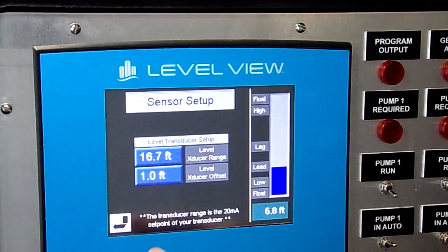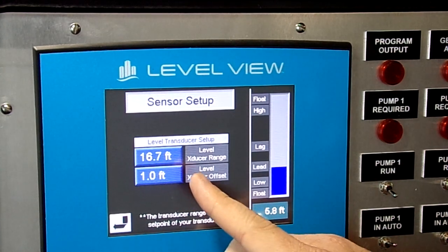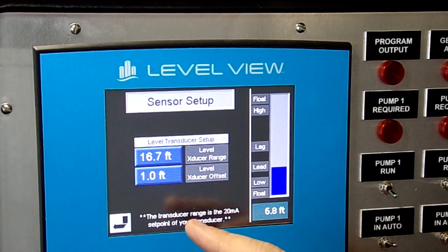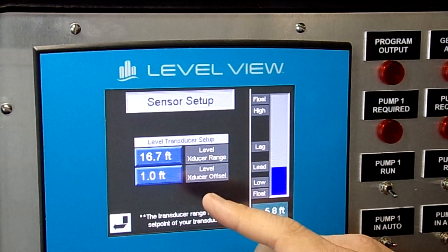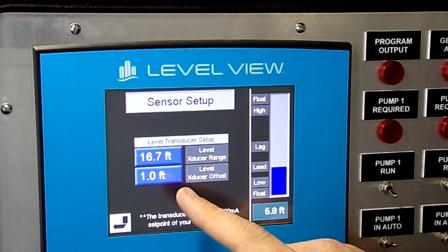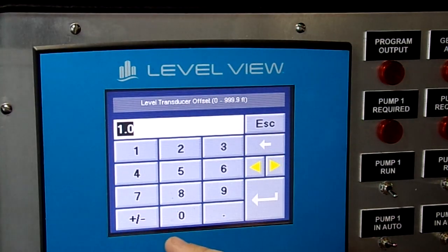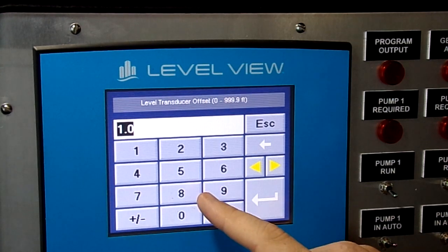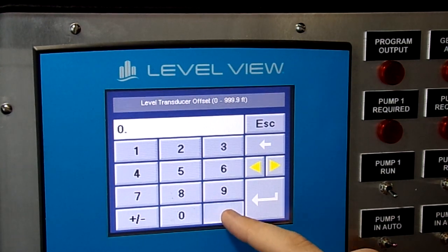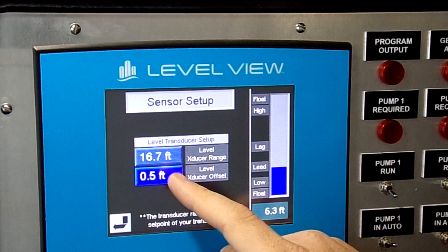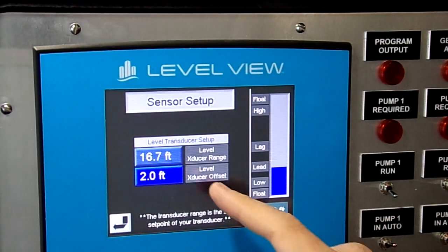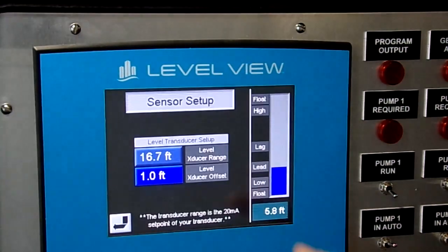Our sensor needs to be set for the sensor range. So if your transducer is set for 16.7 as its maximum range, that needs to be inserted in here. If it's 30 feet or 100 feet, etc. We also have an offset. The offset needs to be set at how far the transducer is off the well. So this can be set at 1/2 foot or 2 foot, but most typical stations we see are usually set at 1.